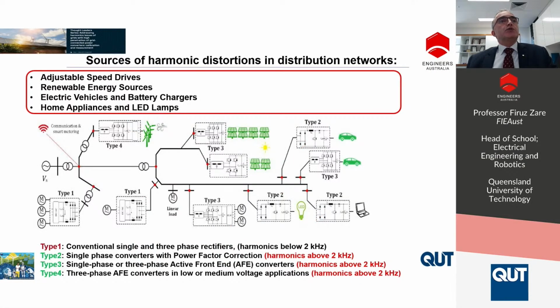Type 1 is based on the diode rectifier. It can be single phase or three phase, and because it's very reliable and cost effective, we still have lots of products in the network. Type 2 is a very special type of single-phase device, and the current waveform is almost sinusoidal with some high frequency harmonics at the switching frequency of the system, and normally the switching frequency is around 30 kilohertz. Type 3 and 4 are low power and high power grid-connected inverters based on bridge rectifiers, and normally the switching pattern is above 2 kilohertz.